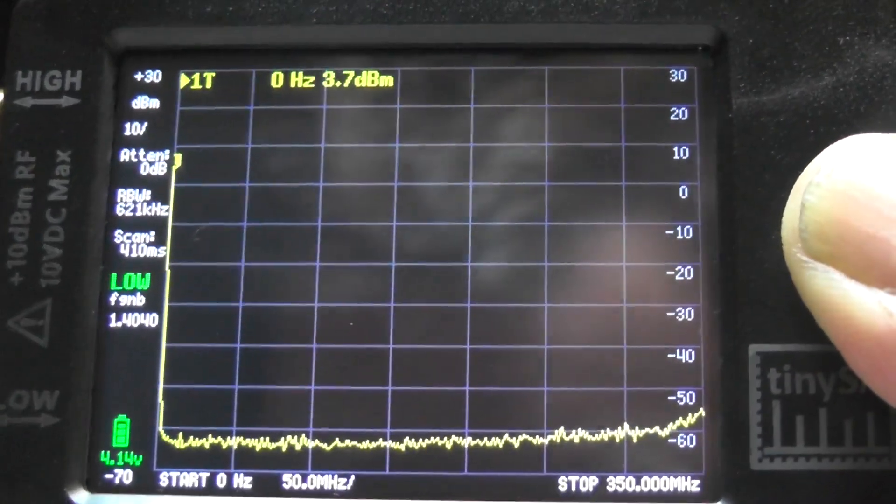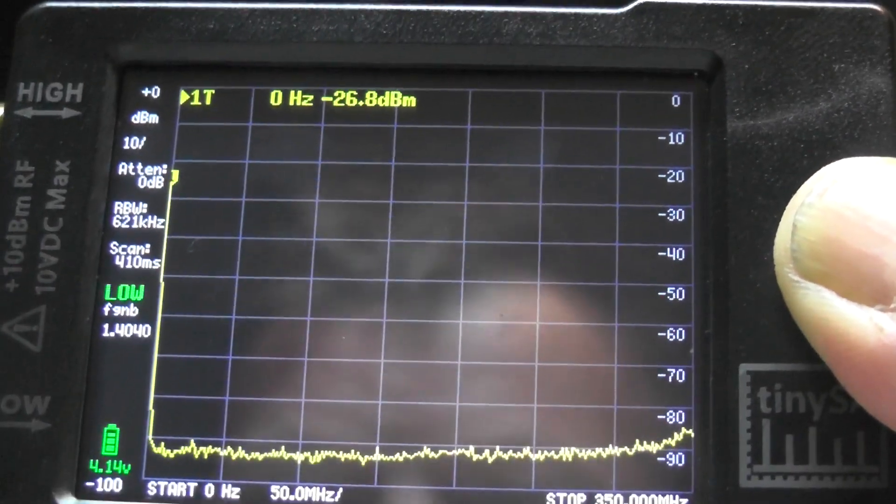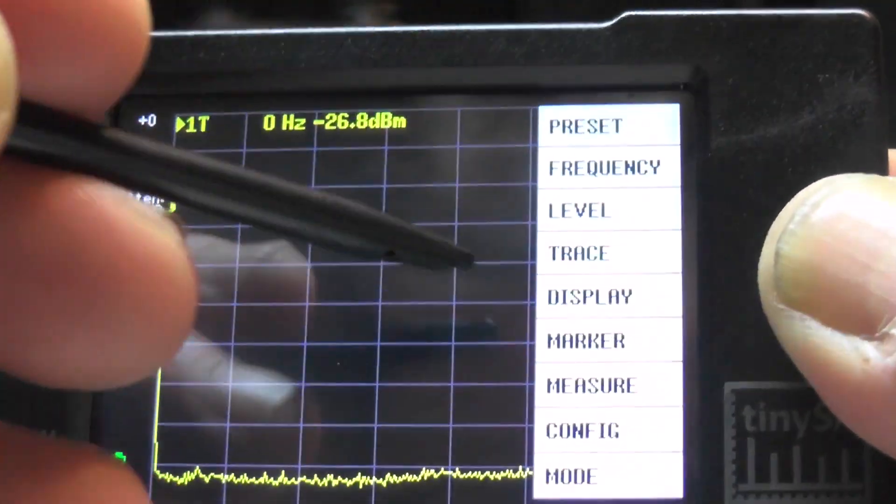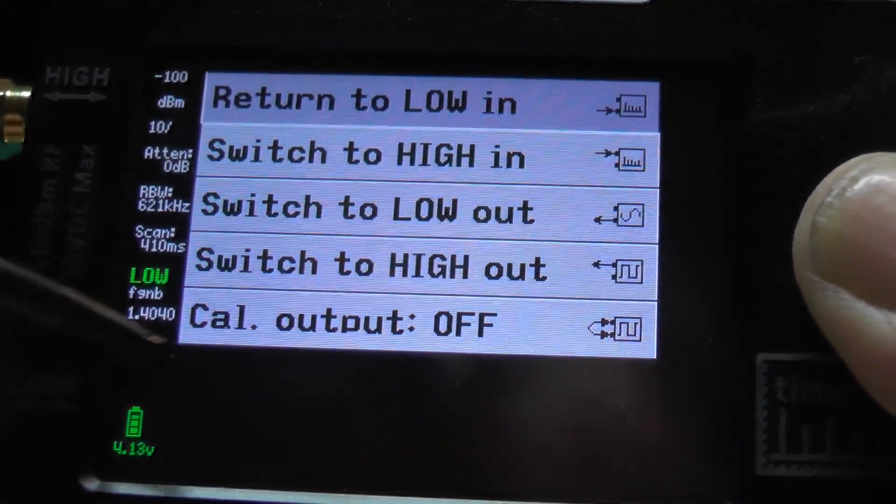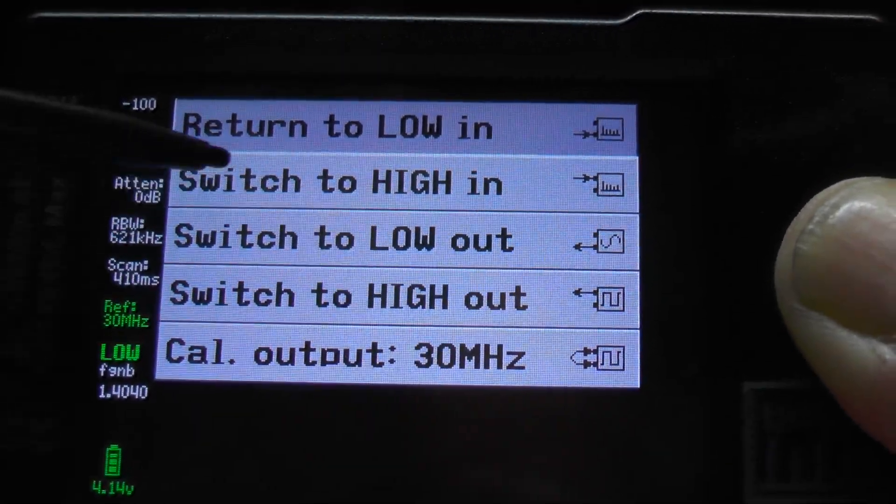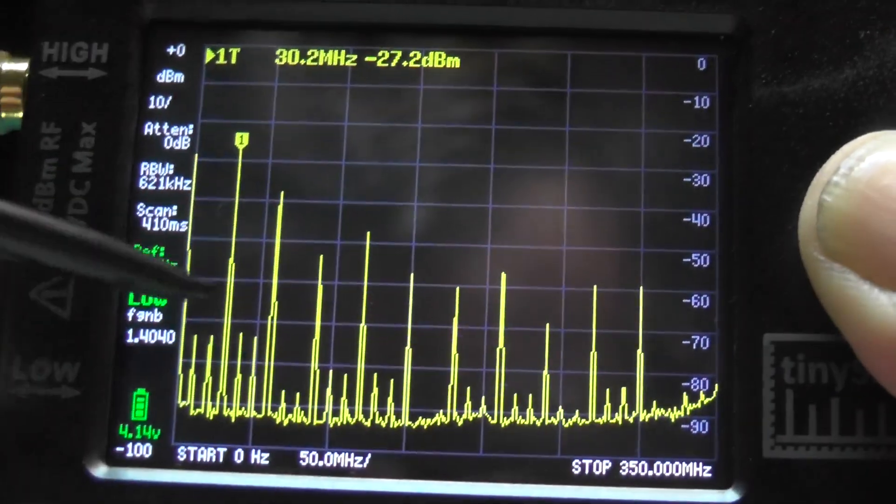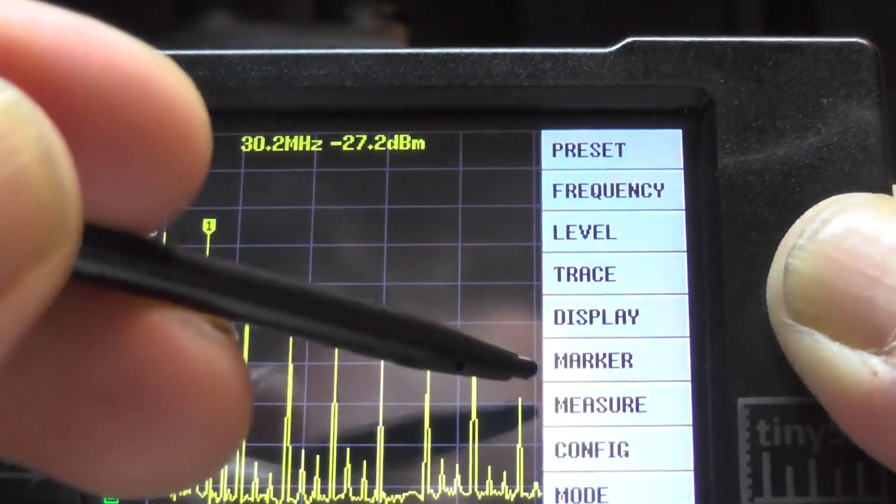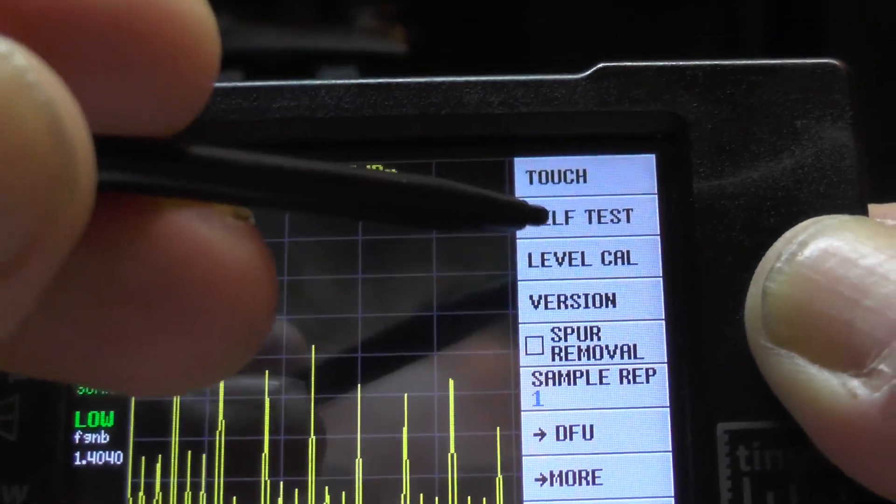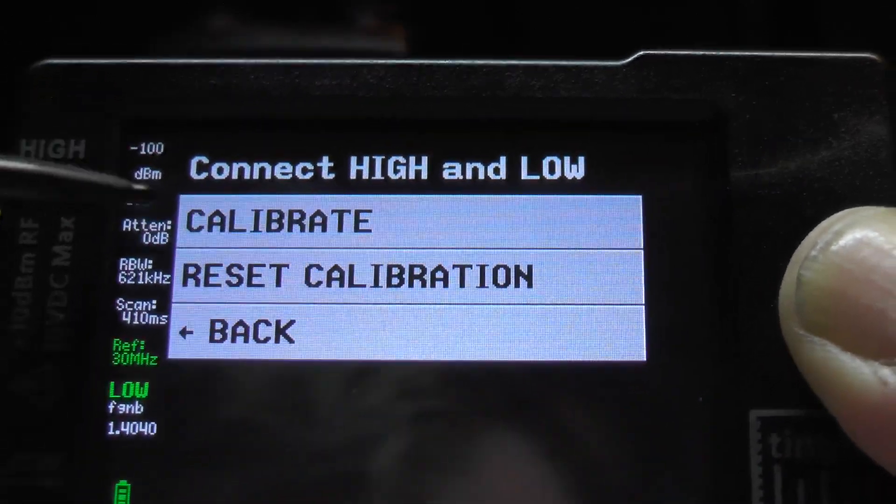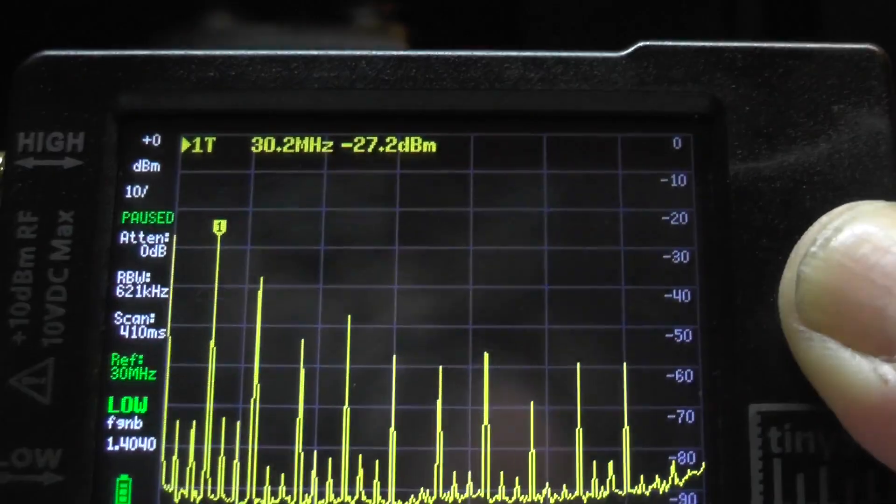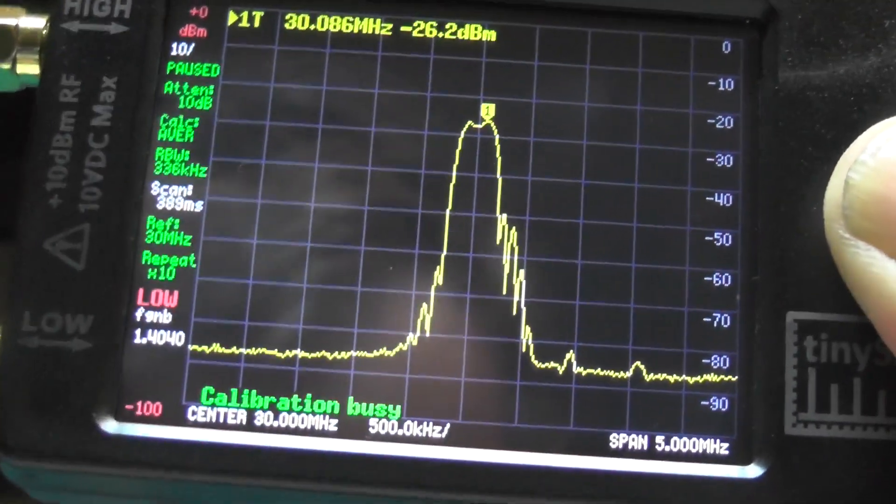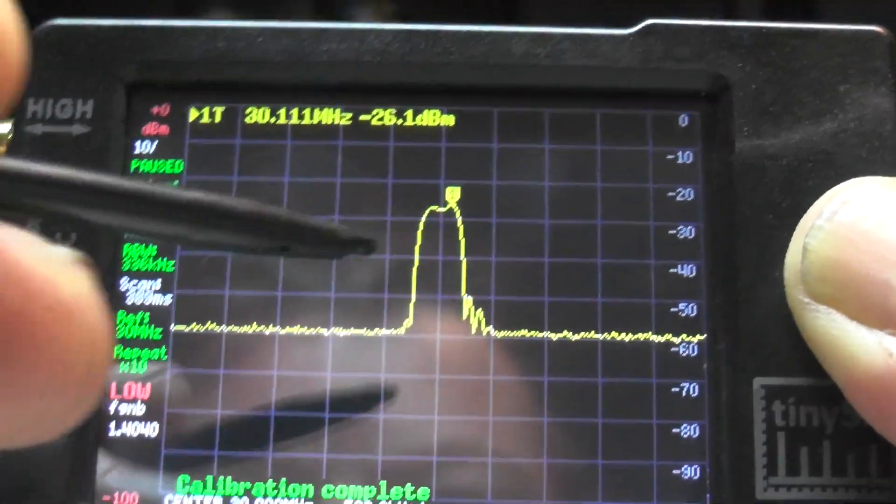Touch the screen. Passed its self test. What we're going to do now is a level calibration. Press on the screen, just go to mode and do calibration. Cal output, there is 30 megs and all that harmonics and stuff coming on there. Tap the screen, go to config and level calibration. You'll see here calibrate, reset calibration, or back. Press on calibrate. There we go, the calibration is complete.